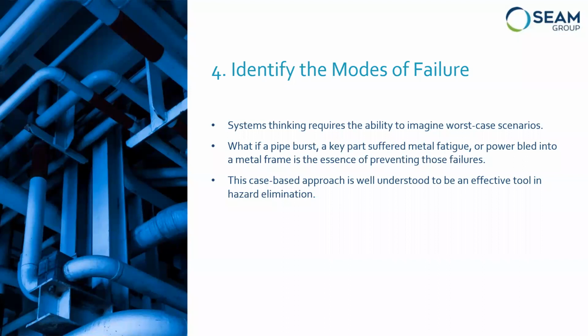And this wasn't part of their normal PM to even look at this. But if left unchecked, those wires would rub against a sharp metal inlet into the motor body. The failure here is that when that motor body wears through that insulation and gets to the conductor, it's going to cause a short, might even cause an arc flash, depending on if multiple wires wear through at the same time or what have you. So if that facility had an arc flash survey and coordination study done, then the breaker upstream should trip, no problem, right? So we have an arc flash potential. Maybe it's not that big because the proper circuit breakers are in place, everything goes according to plan, anyway, maybe not well.